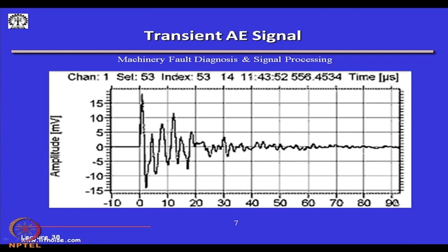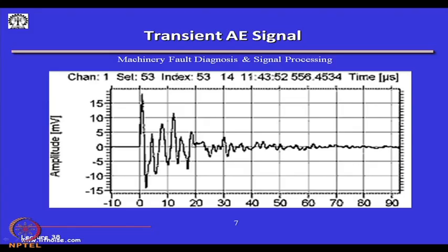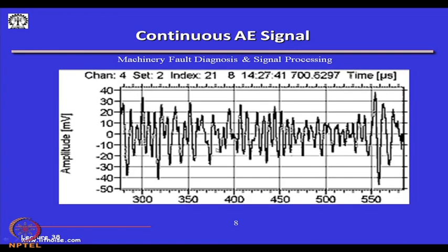This has to be captured on a device such as a digital storage oscilloscope. From this time-domain signal, certain features could be found out: number of peaks beyond a certain threshold, number of peaks occurring in a time period — all this could be done through a simple analog processor. As opposed to the transient burst signal, a continuous AE signal shows some sort of energy in a particular time waveform.